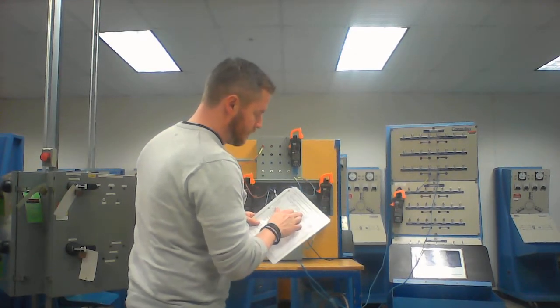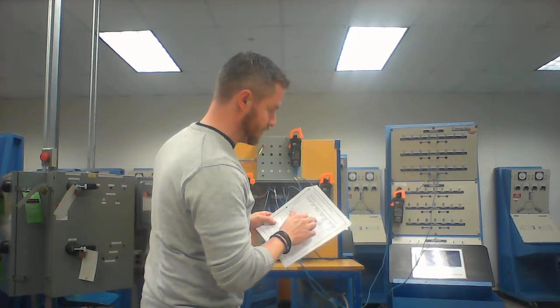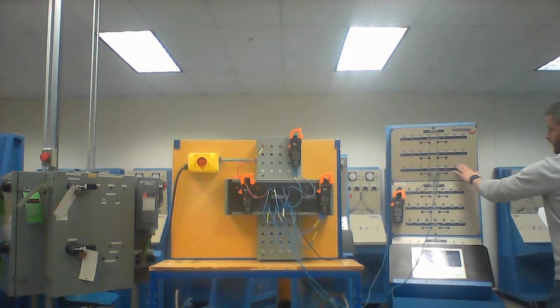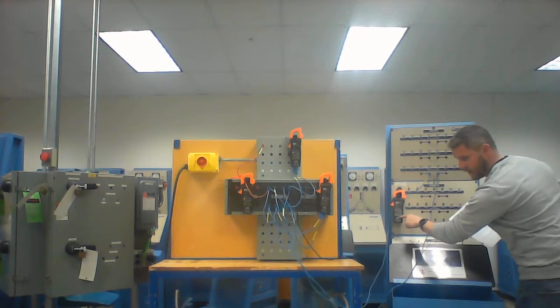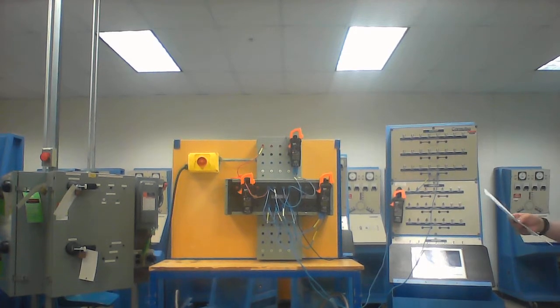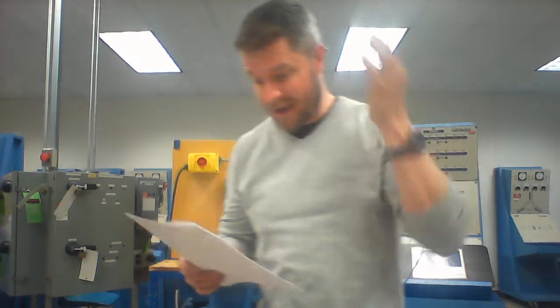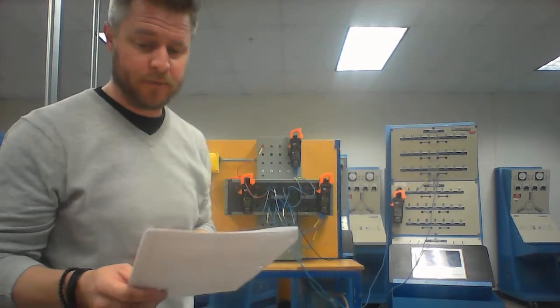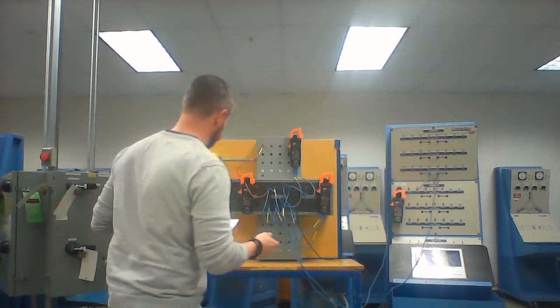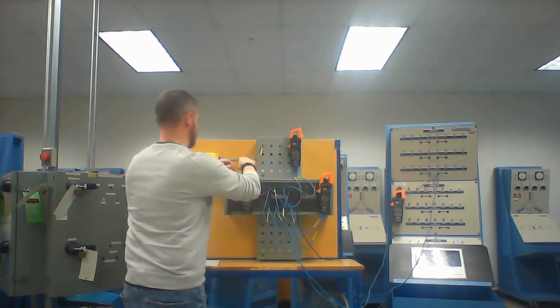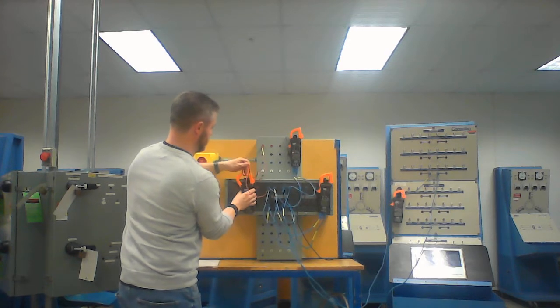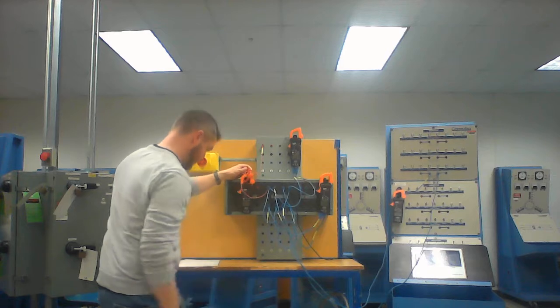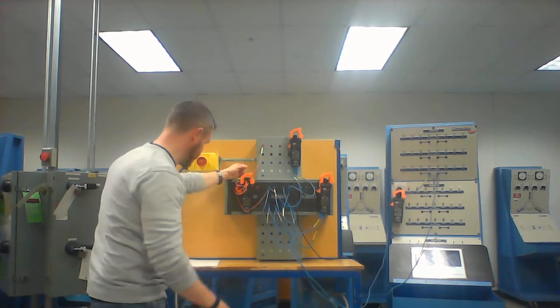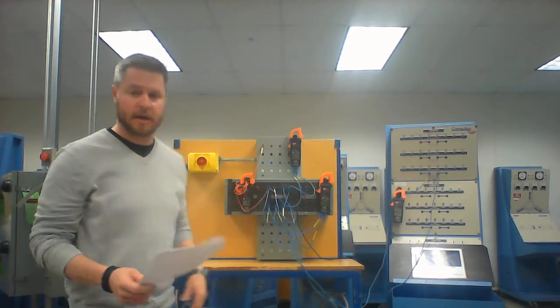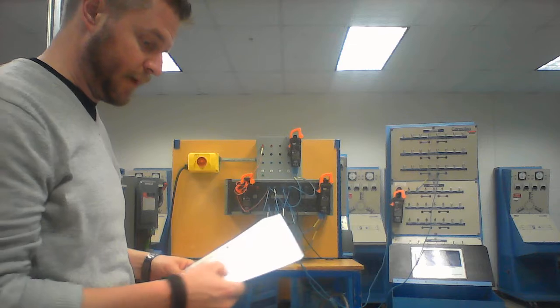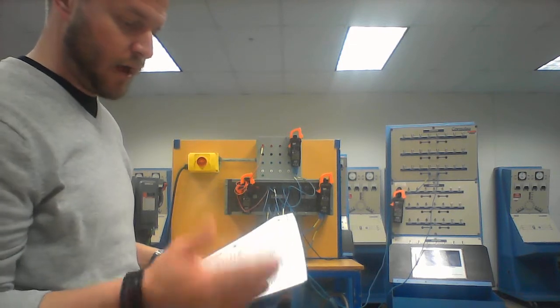No load value, I'm not going to have a measured secondary current. That's going to be 0 amps, right? Even if I look at it over here, I don't have anything connected yet. All these resistors are still turned off. I have 0 amps current flow for a measured secondary. Calculated primary current using the measured secondary and ratio. That's going to be excitation only, so that's around 100 milliamps. Measured primary current. Go back to my 10-turn coil, or 6 turns, I guess is what I had. Yeah, 100 milliamps, 0.63 amps times 6 turns through the amp clamp. Okay, that's my measured primary current, and then we'll look at the difference between your measured and calculated a little later on.